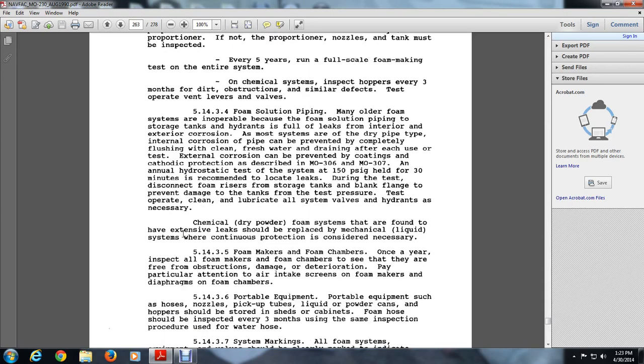5-1-4-3-5, foam makers and foam chambers. Once a year, inspect all foam makers and foam chambers to see that they are free of obstruction, damage and deterioration, paying particular attention to the air intake screens of foam makers and the diaphragms of foam chambers. 5-1-4-3-6, portable equipment such as hoses, nozzles and pickup tubes, liquid foam concentrate cans and hoppers should be stored in sheds and cabinets. Foam hoses should be inspected every 3 months using the same inspection procedure used for a water hose.